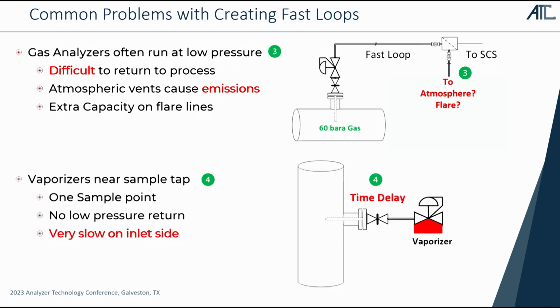And then yet another problem, in a place where we often don't put a fast loop in but we really need one, is near vaporizers. If we're putting a liquid vaporizer in near the sample tap, we would really like to have a fast loop in front of it, because vaporizers take very, very low liquid flow rates. If you look at a vaporizer that's running about 1 liter a minute of gas on the gas phase side, it might only be vaporizing 2 or 3 milliliters a minute of liquids. And again, since time is volume divided by flow rate, if we have very low flow rates on the inlet to the vaporizer, we can have very long time delays. Usually, if we have time delays in a liquid system that's using a vaporizer, the time delay is happening on this side of the system.